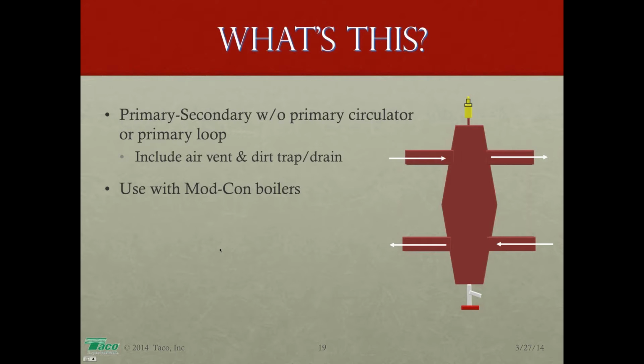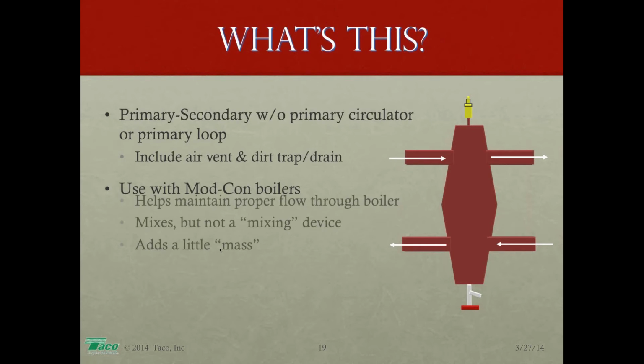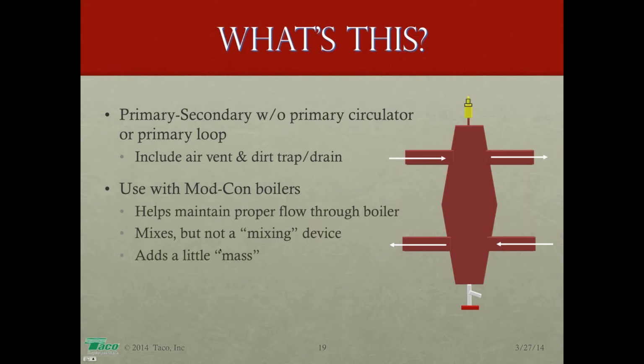Okay? And when you use it with a ModCon boiler, it helps maintain the proper flow through the boiler, as we said. Mixing takes place in here, as it does in those closely spaced tees, but of course it's not a mixing device. And it isolates the two. So flow through here is not going to interfere with flow through the boiler, and flow through the boiler is not going to interfere with flow through the distribution system. Okay? It does also add a little bit of mass to the system, a little bit of water content, depending upon which ones you buy. And that's also very important with ModCon boilers.